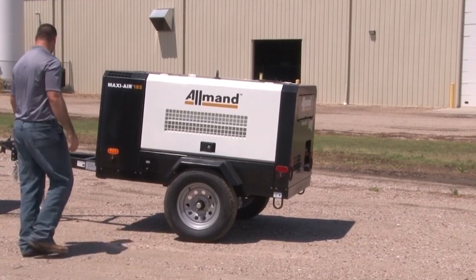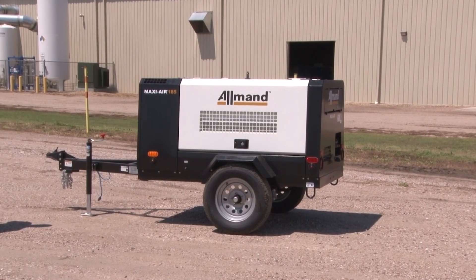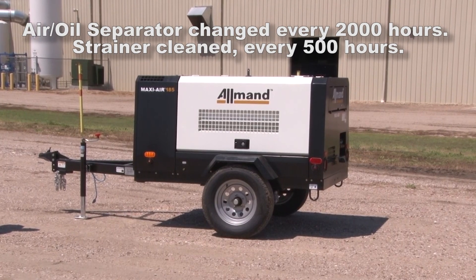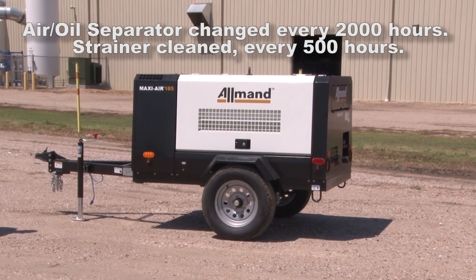Accessible and reliable compressed air is essential to the work that you do. With proper maintenance, Allmand MaxiAir portable compressors will be ready for you when you need them the most. The air oil separator should be changed every 2,000 hours of usage, with the strainer being cleaned every 500 hours.